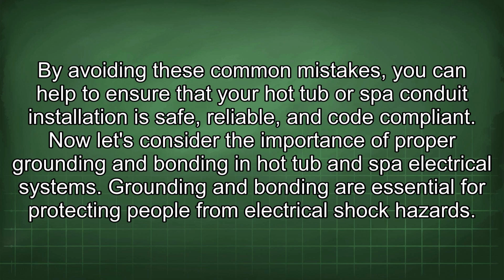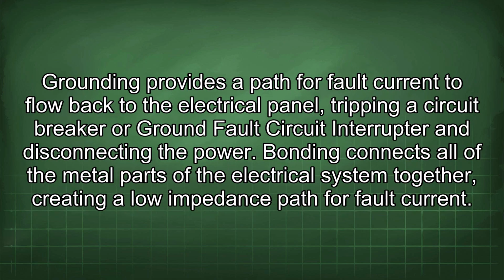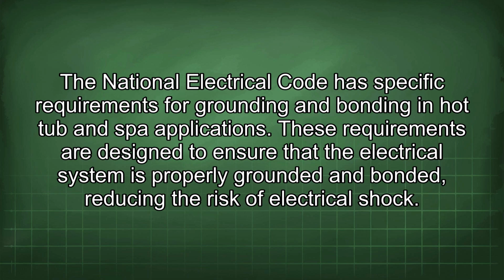Now let's consider the importance of proper grounding and bonding in hot tub and spa electrical systems. Grounding and bonding are essential for protecting people from electrical shock hazards. Grounding provides a path for fault current to flow back to the electrical panel, tripping a circuit breaker or ground fault circuit interrupter and disconnecting the power. Bonding connects all of the metal parts of the electrical system together, creating a low impedance path for fault current. The National Electrical Code has specific requirements for grounding and bonding in hot tub and spa applications.